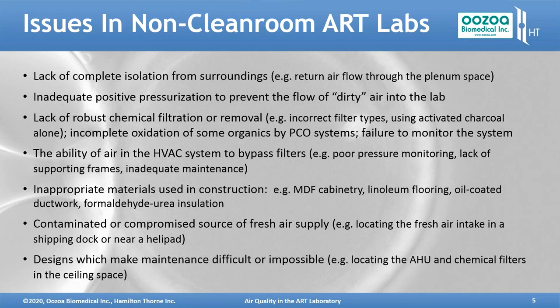Here, like cabinetry made of MDF, medium density fiberboard, or using linoleum for floor covering, or oil coated ductwork, and the oil coating is used for rust prevention, or formaldehyde urea insulation. You often have a contaminated or compromised source of fresh air supply, and examples from the real world include having built labs where the fresh air intake is in the shipping dock, or it's near the helipad. You know, the lovely smell of aircraft fuel in the lab every time the helicopter lands or takes off. Or you have designs which make maintenance difficult or impossible. For example, some places might locate the air handling unit and the chemical filters inside the ceiling space of the lab, and that's very difficult to get at to maintain.